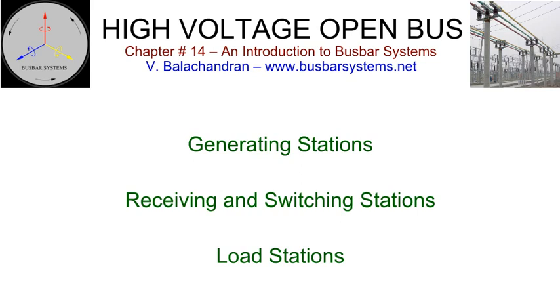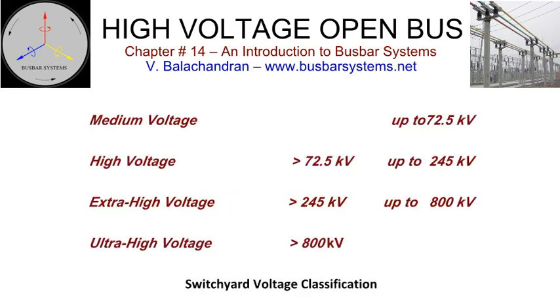Load stations are where the power is consumed by major load centers such as process plants, mining and extraction plants, utilities, and urban areas. Many consumers may have captive generation within the plant to cater to the load and export power to the grid during lean demand. Switchyards are characterized by the rated voltage. Countries all over have adopted different voltages for power transmission and distribution.